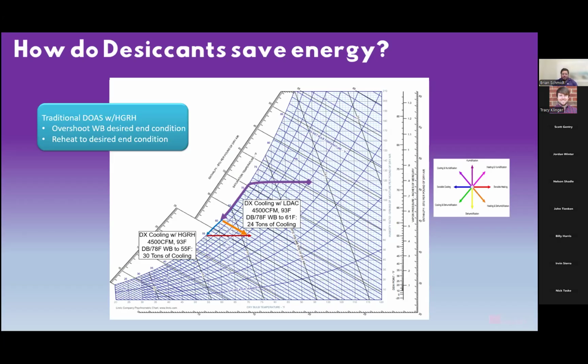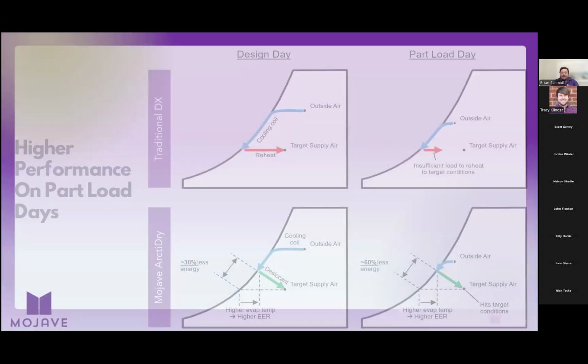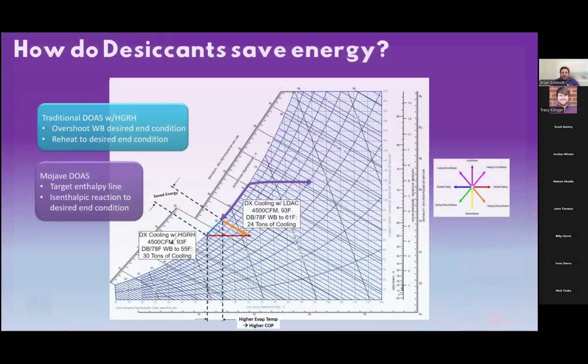Now, for those of you that are very in tune with scientific terminology, this is an isenthalpic process. What that means is for every bit of latent that we are picking up, we are giving off sensible. So we don't have hot gas reheat because we don't need it. We do pick up about a 10 to 12 degree delta off of our pad that I'll show here in a little bit. So again, we're going to cool down to about 60, 61 degrees, allow that isenthalpic process through dehumidification to take over, and we're going to follow that line of enthalpy down to our space conditions.